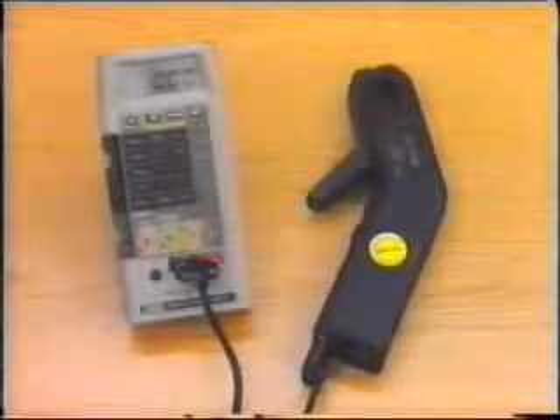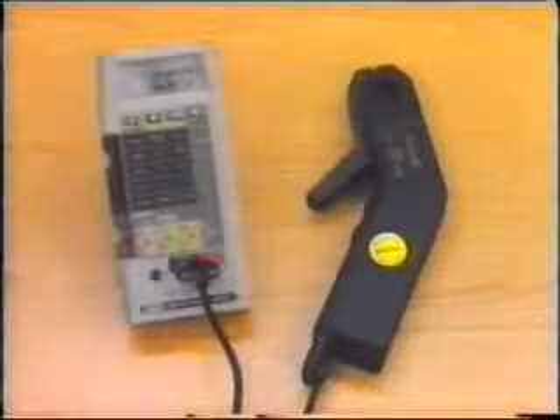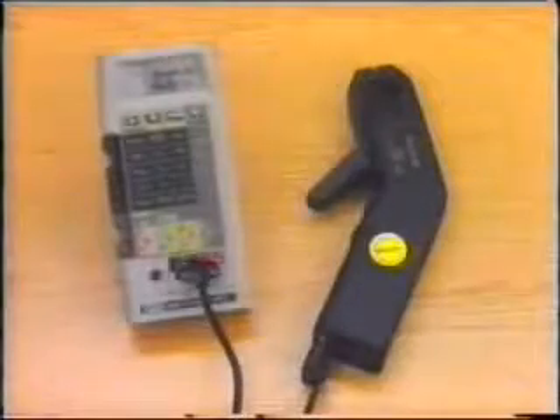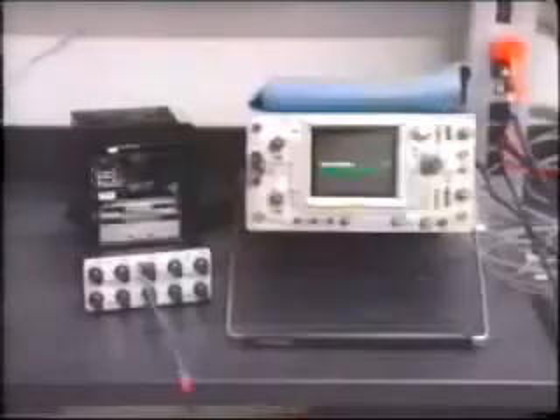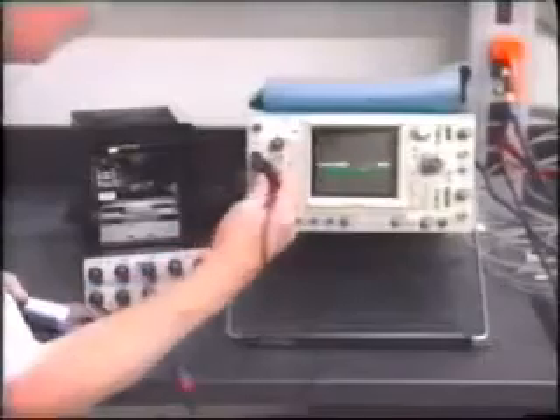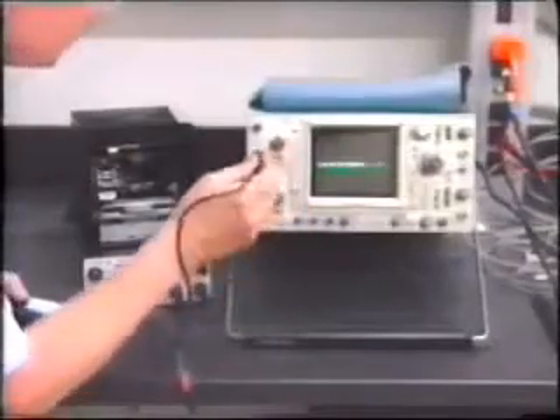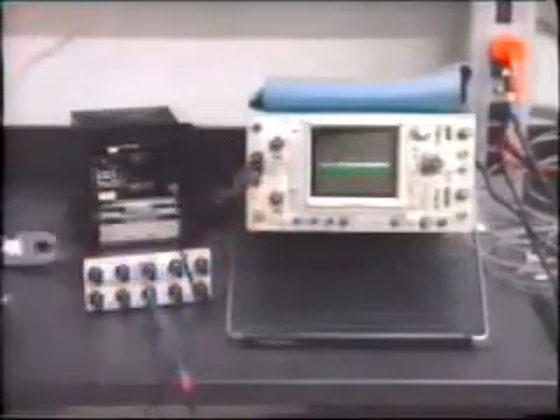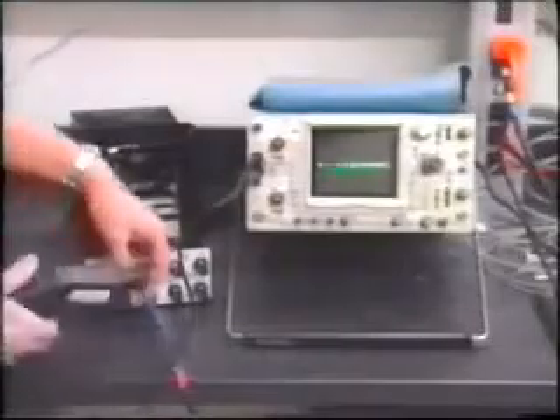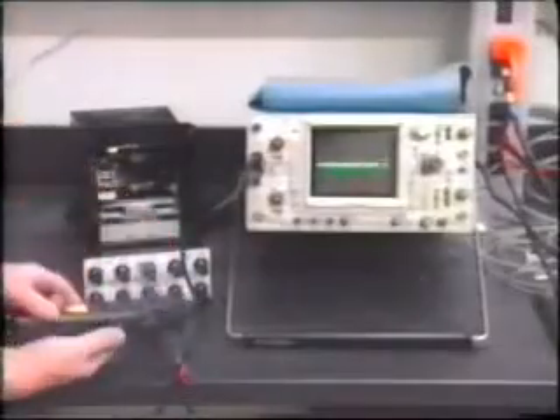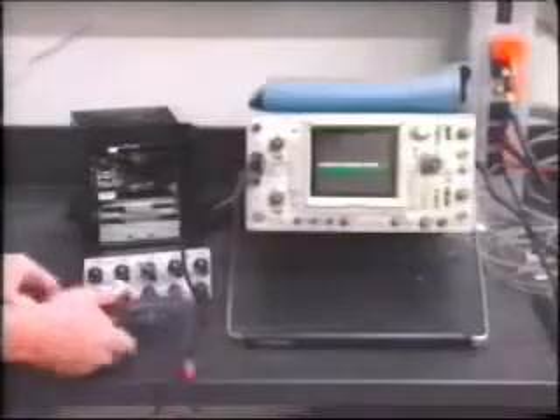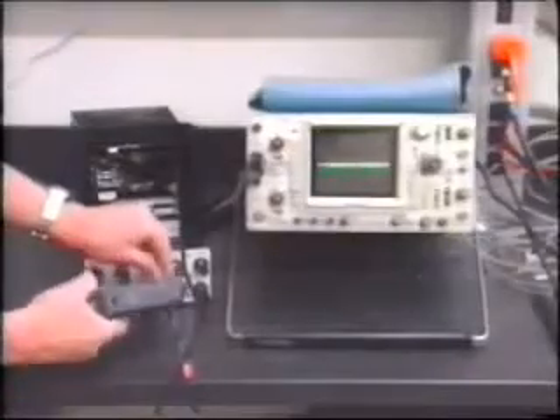You will remember that in segment A, the Hall effect clamp-on current probe was discussed for use with a digital multimeter. It turns out that this probe, because it converts a current input to a voltage output, works fine with an oscilloscope. You simply clamp it onto a current wire feeding the relay and connect its output terminals to the vertical input of the oscilloscope.